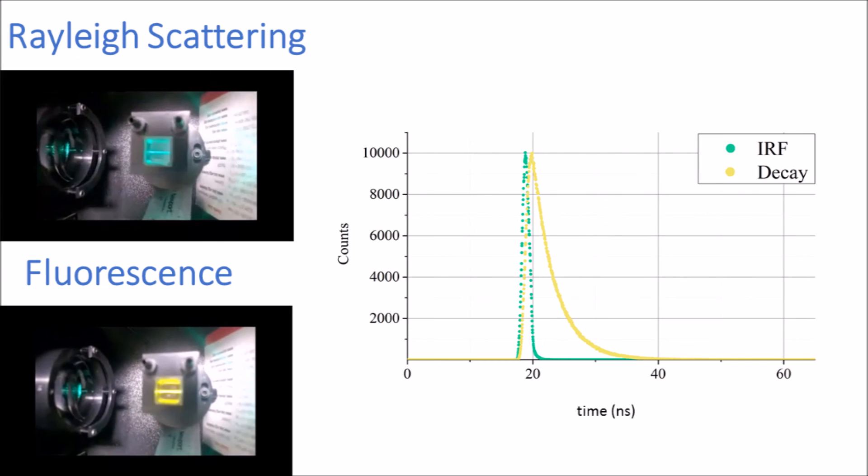The histogram shown was quite a crude one. In most measurements, we would measure to a peak count of at least 10,000 counts, and we would typically have at least 500 bins per fluorescence decay.